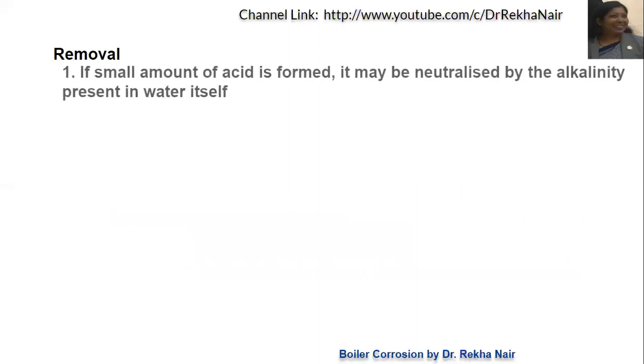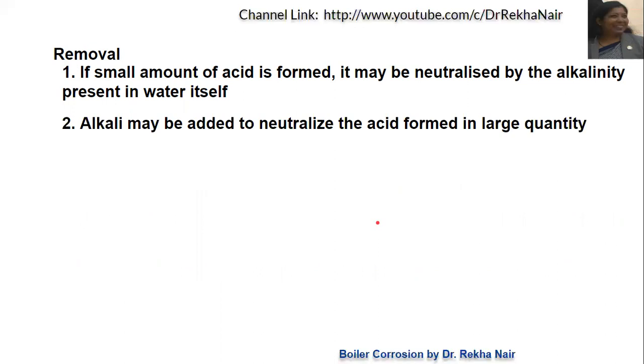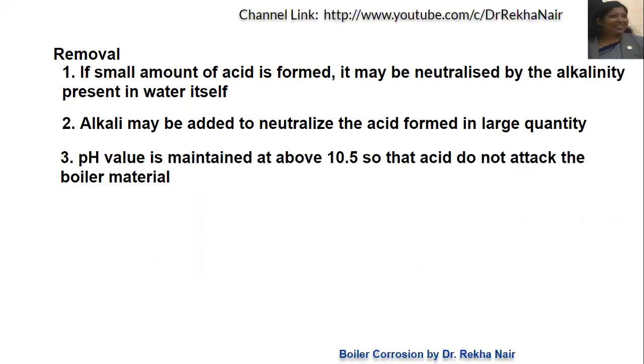For removal of acids, if there is a small amount of acid present, we can add some alkali to neutralize it in the water. If acid is formed in large quantities, alkali may be added to neutralize it. The pH is maintained at about 10.5 so that acid does not attack the boiler material. Maintaining this alkaline pH above 7 ensures acidity will not be a problem.